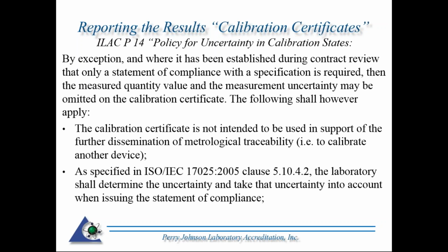And it states the following. By exception, and where it has been established during contract review that only a statement of compliance with a specification is required, then the measured quantity value and the measurement uncertainty may be omitted on the calibration certificate.